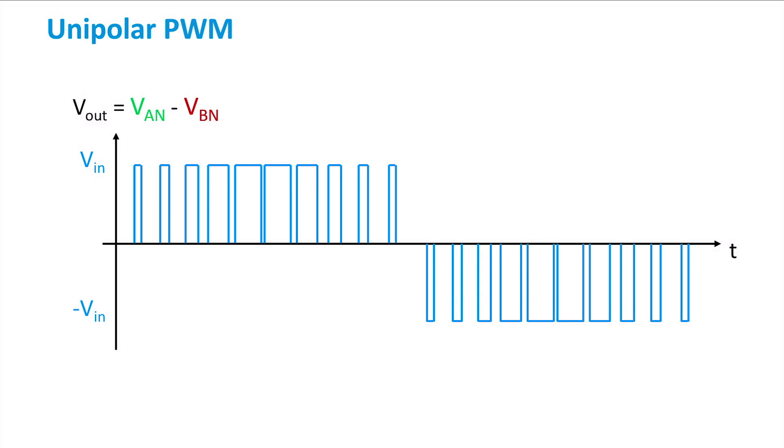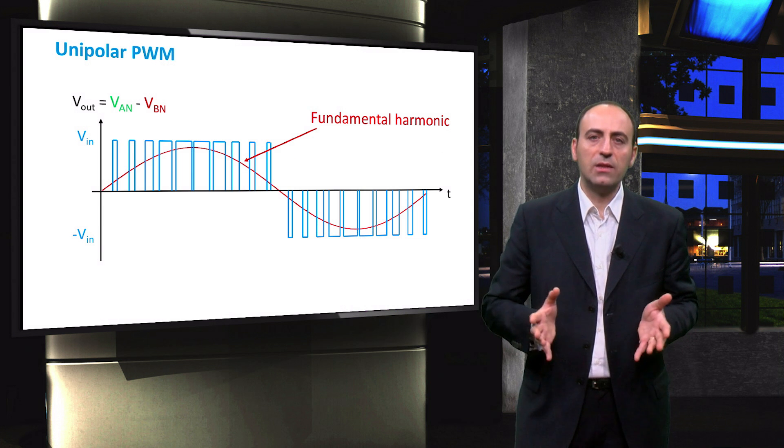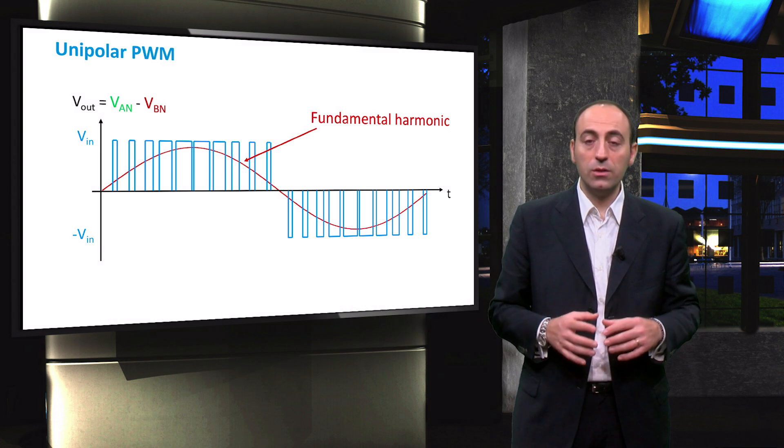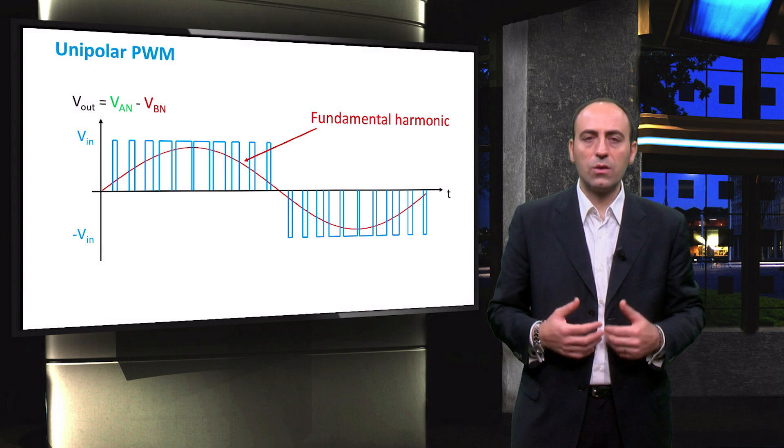Just like the bipolar case, a pure sine can be drawn from a Fourier analysis of the output signal. This sine is the fundamental harmonic which carries the real power delivered by the inverter. The most important advantage of the unipolar PWM scheme over the bipolar one is a lower harmonic content which translates into less signal distortion that needs to be filtered by the inverter.